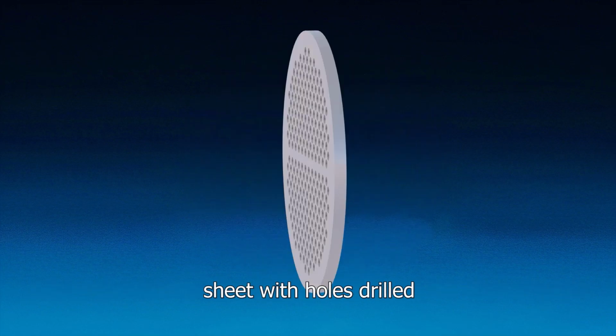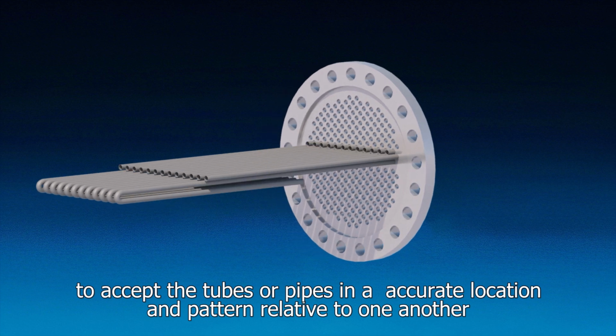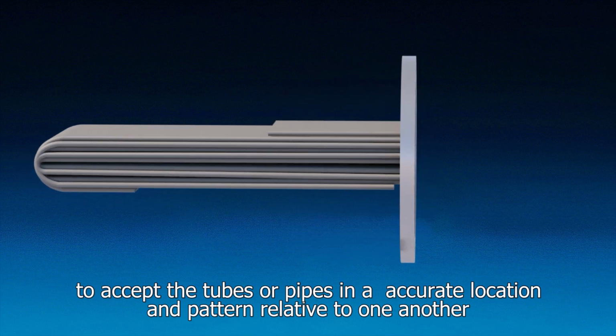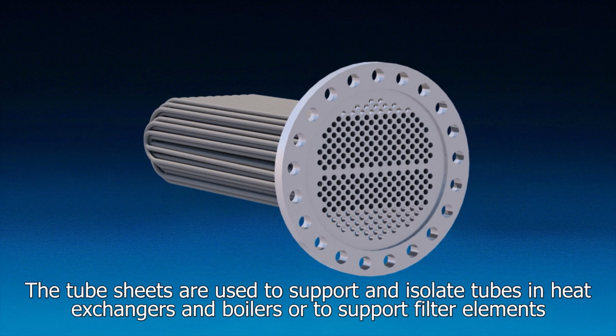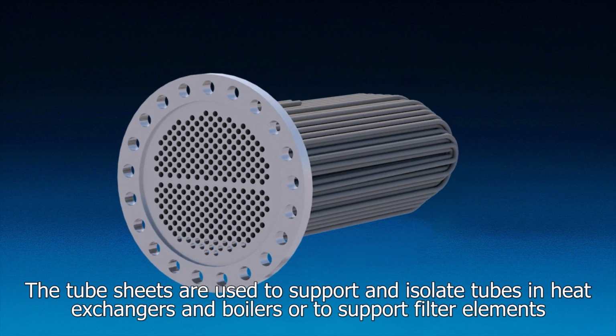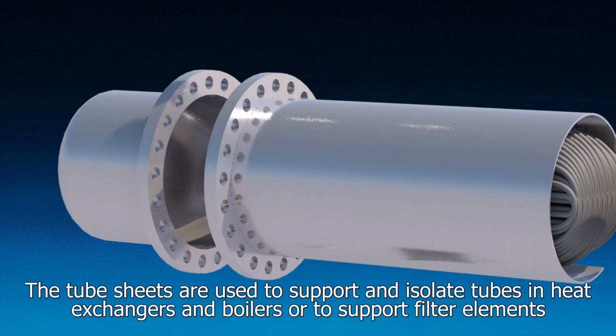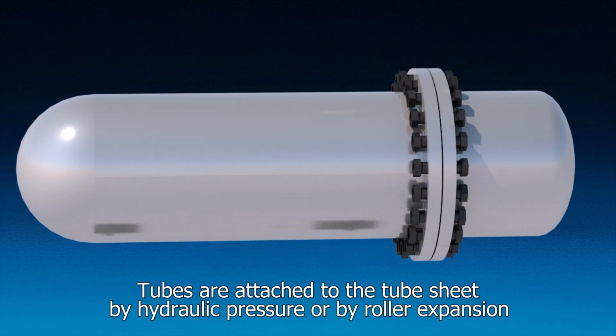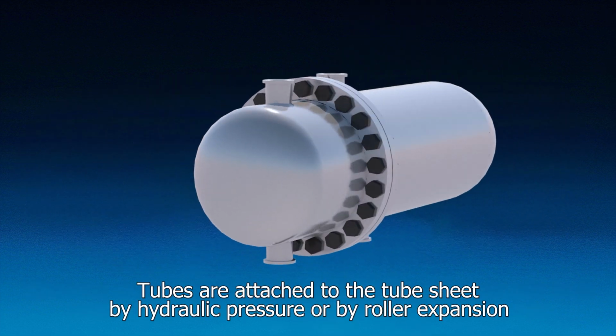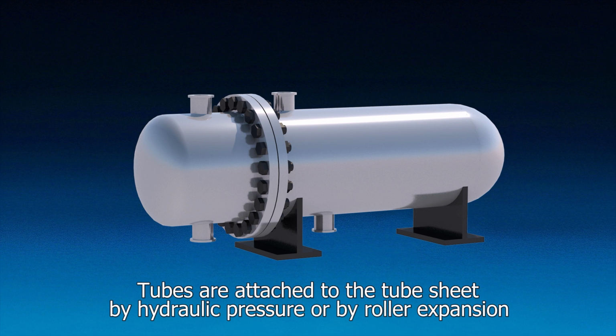A tube sheet is usually made from a round flat piece of plate, sheet with holes drilled to accept the tubes or pipes in an accurate location and pattern relative to one another. The tube sheets are used to support and isolate tubes in heat exchangers and boilers or to support filter elements. Tubes are attached to the tube sheet by hydraulic pressure or by roller expansion.